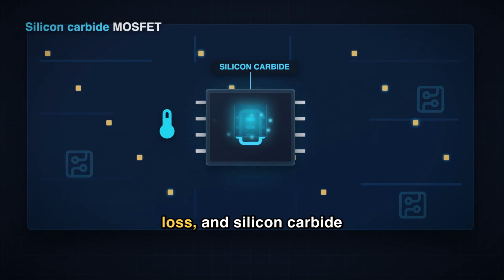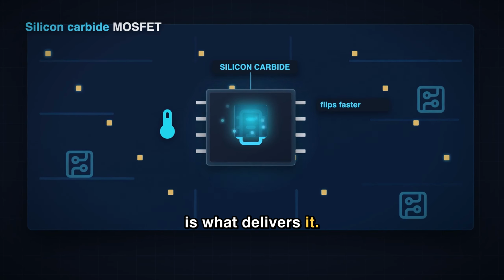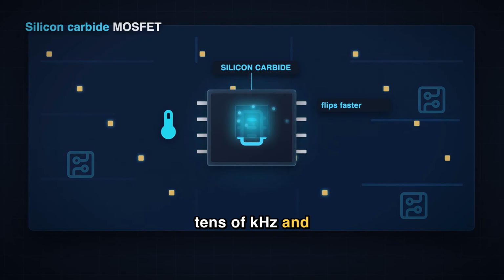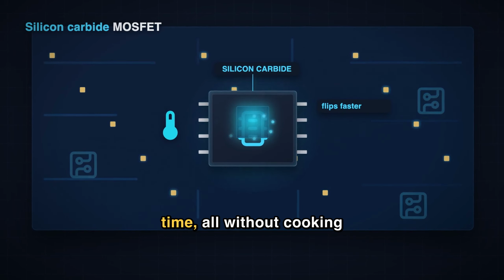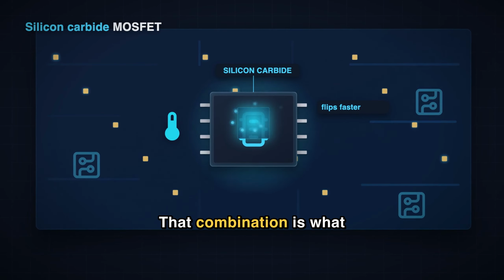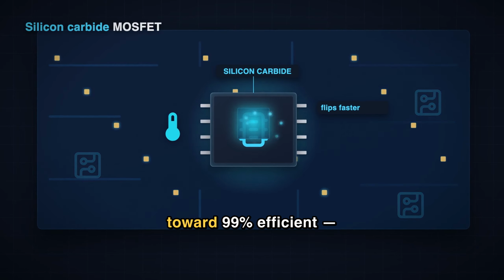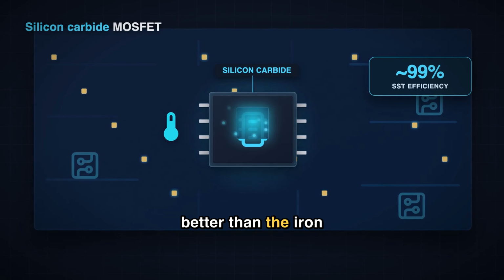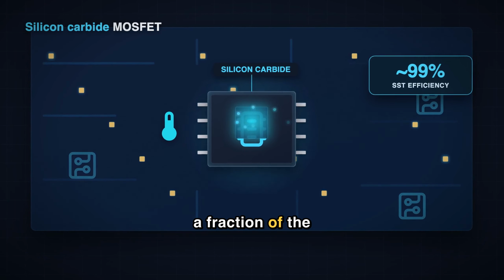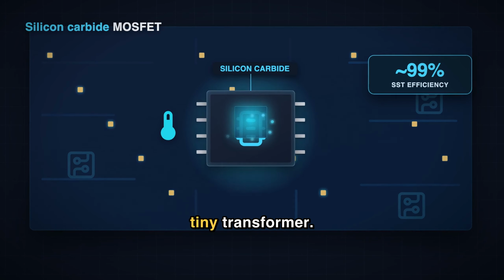Speed needs low switching loss, and silicon carbide is what delivers it. Run the chopping at tens of kilohertz and hold off thousands of volts at the same time, all without cooking itself. That combination is what pushes the whole box toward 99% efficient, better than the iron block it replaces, in a fraction of the space. So we have a fast switch and a tiny transformer.